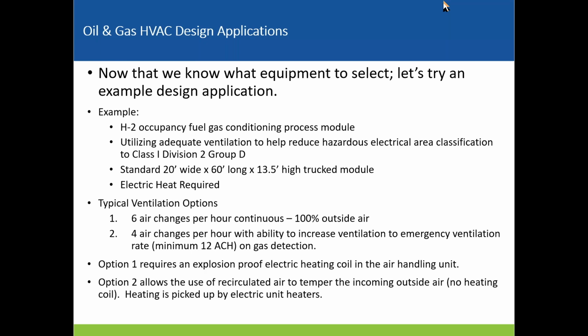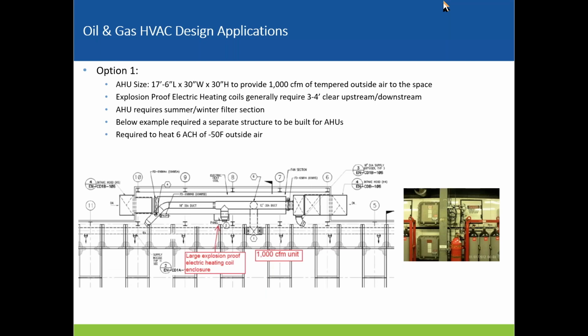So option 1 obviously would require an explosion-proof electric heating coil in the air handling unit. Bring in 100% outside air, we're going to have to heat it somehow. Option 2 allows us to use recirculated return air to temper the incoming outside airstream. So no heating coil is really required. Heating can be picked up by remote electric unit heaters in the space to avoid a really big explosion-proof electric heating coil in your air handling unit.